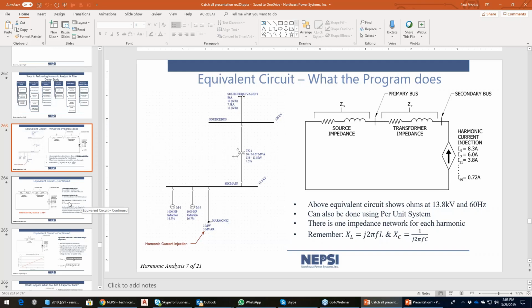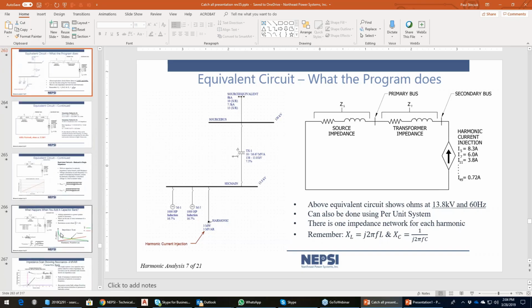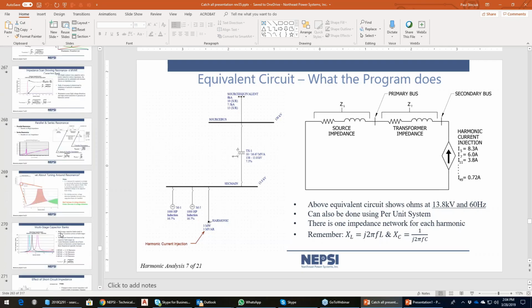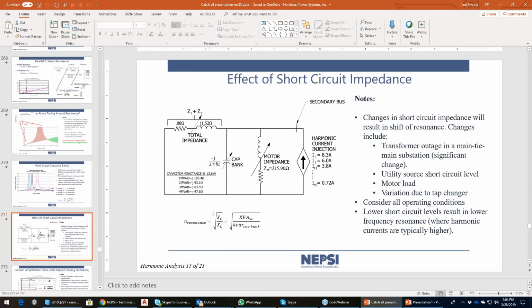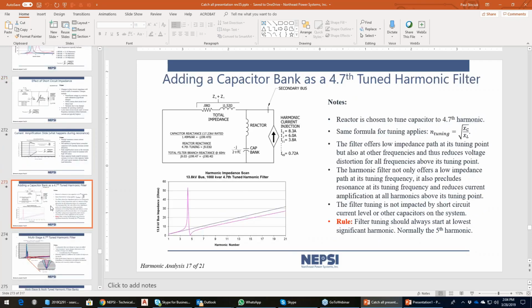If you already had harmonic filters in the system, it would mean that more harmonic current would flow into the filter bank if you were to add impedance. So what you have is, I'm going to slide over to this slide here. If you add impedance here, which is effectively what you're doing, it means you're decreasing the short circuit current. It means that, by the current divider rule, you're going to push more current into your filter.